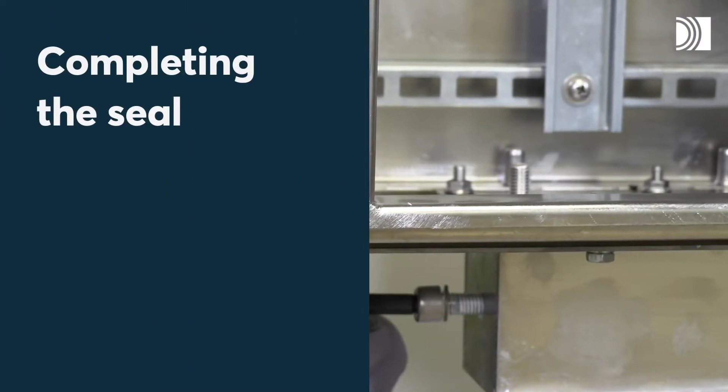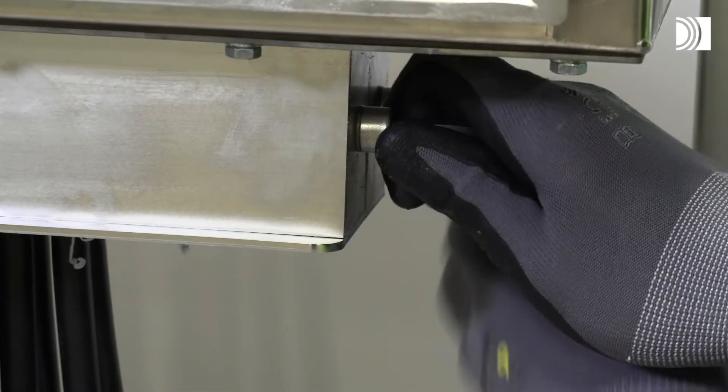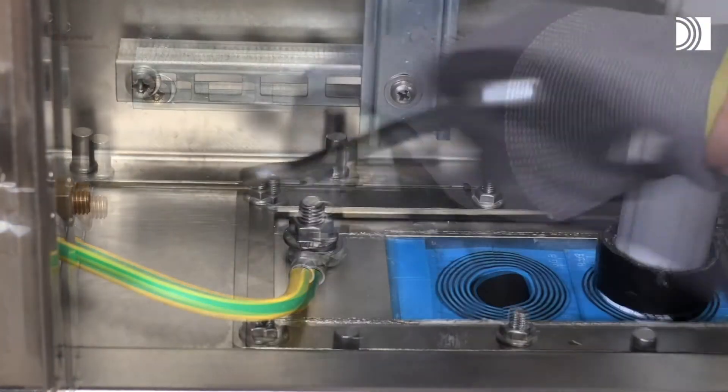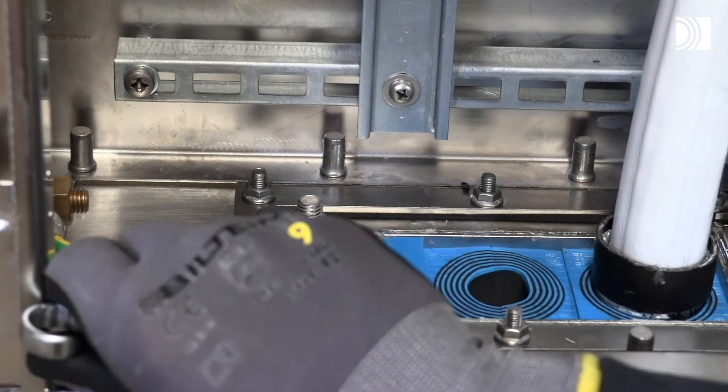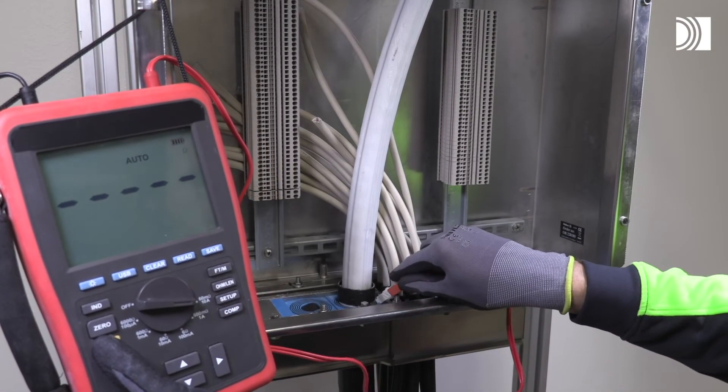Completing the seal. Tighten the screws of the three compression units to full mechanical stop. Attach the protective bonding conductor to the frame. Verify earth continuity from each cable armor to earth by using a suitable instrument.